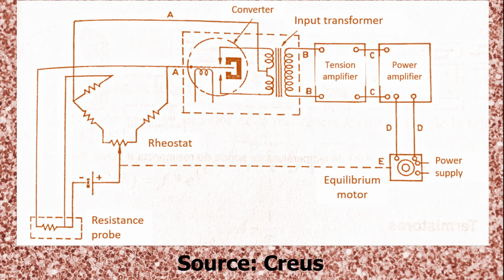Classical automatic measurement of resistance, and therefore temperature, is carried out by self-balancing instruments using a Wheatstone bridge circuit. The resistance probe is connected to the bridge by 3 wires. If the bridge is unbalanced, the error signal in the form of direct voltage that appears in the image as AA is converted to an alternating voltage, BB, and amplified in voltage CC and power DD to excite the balance motor E. This moves in the suitable direction to balance the bridge through the mobile arm of the rheostat, which at the same time actuates the indication, register, and control mechanisms.